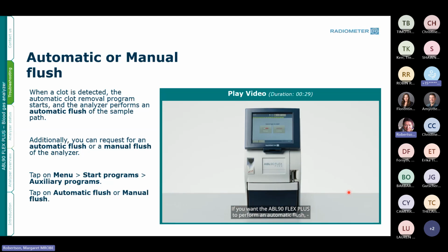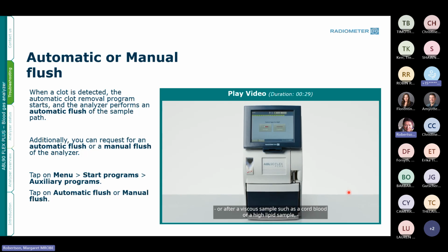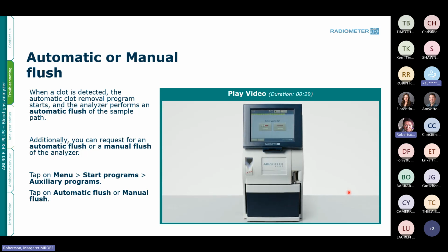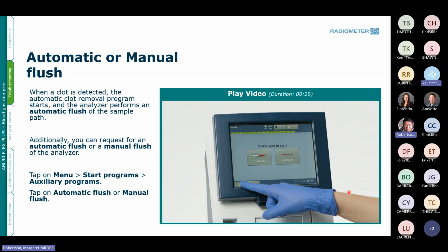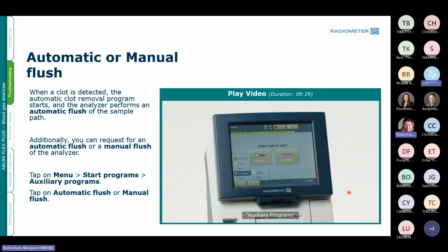if you want the ABL90 Flex Plus to perform an automatic flush, for example, during troubleshooting or after a viscous sample such as cord blood or a high lipid sample, follow these steps. Tap Menu, Start Programs, Auxiliary Programs, Automatic Flush. The analyzer will then perform an automatic flush.